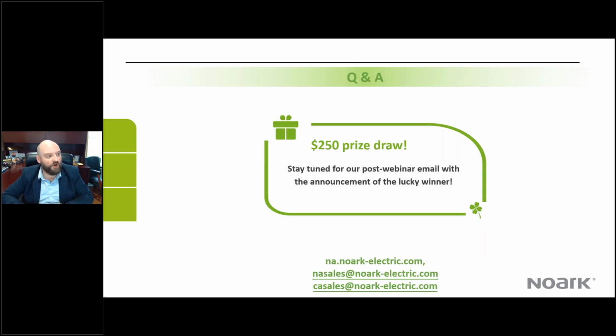No, thank you for that. A question just came in: what communication protocols do your circuit breakers support? Like Modbus TCP? Yeah, I'll take that one. The breakers typically come with RS-485 Modbus protocols. We do have some gateway products that will do some translation, but the native protocol for the breakers is RS-485 with Modbus.